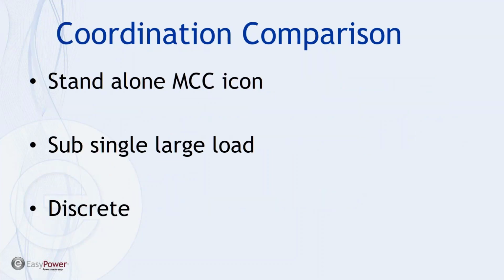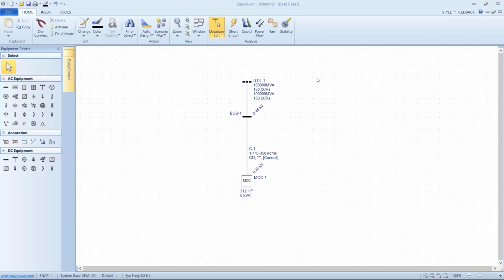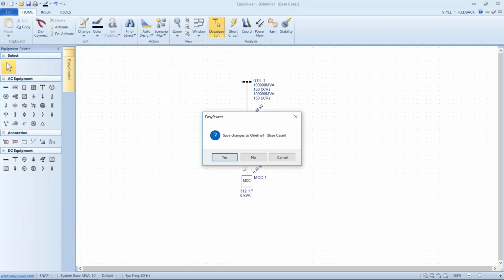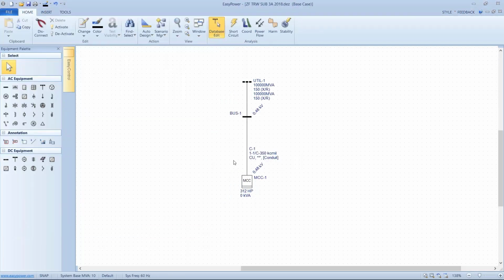So now what I want to do is do a comparison of coordination on a more complicated system invoking a standalone motor control center, and then in one case we're going to outboard a single large load from that motor control center and compare it with the results we get from doing a discrete version of it. So let's go back into EasyPower. Let's close this and not save it. Let's close this one and not save it.